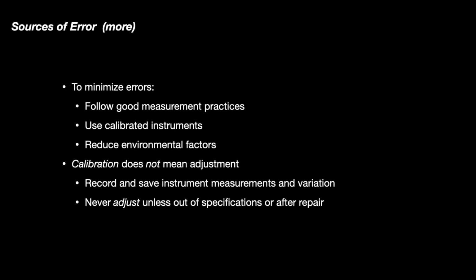So, there's a range around things. We'll get into that a little bit when we talk about the individual instruments. So you never adjust unless the machine has been repaired or it's out of specification. If it's out of specification, it goes down to the Cal Lab, and they either adjust it or they say that it cannot be adjusted. This happens sometimes.